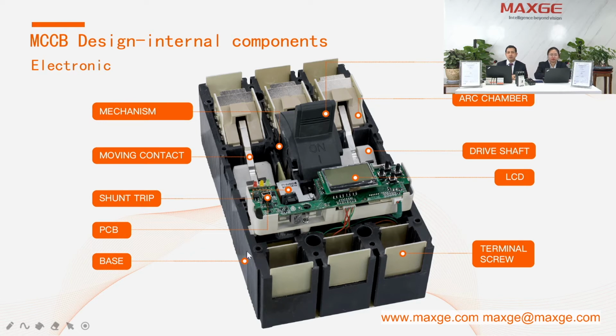This is the base, which is made of a dough molded compound or a sheet molded compound, which is very strong material, unaffected by temperature or fire. It is actually a fire resistant material. These are the terminal screws. Here is an LCD, so all the parameters and protection parameters can be displayed here. Here is a drive shaft, where the moving contacts are connected. And here is the arc chamber. This is a unique design of arc chamber, used for quick quenching of the arc. And here is the knob. Our knob design is very ergonomic, so for the end user it's very comfortable to switch the MCCB on and off.